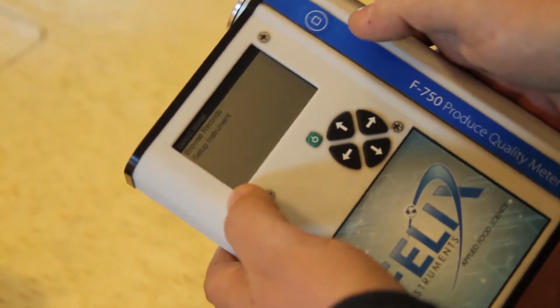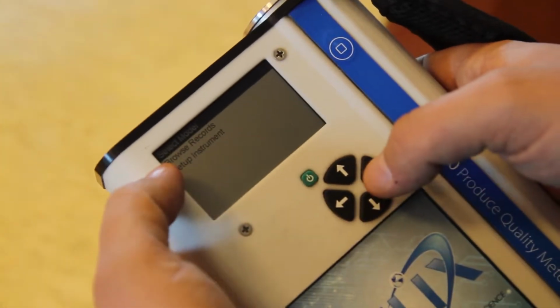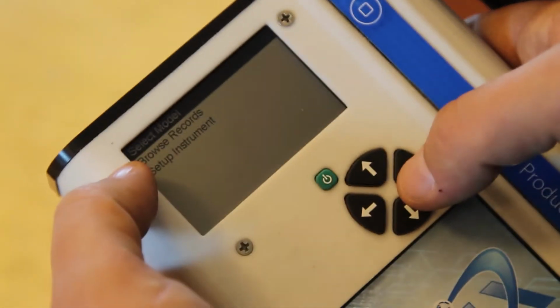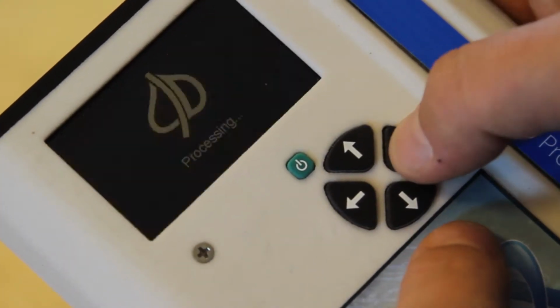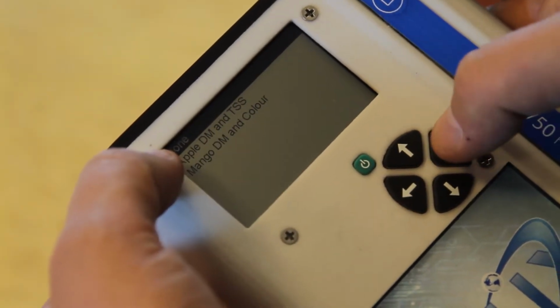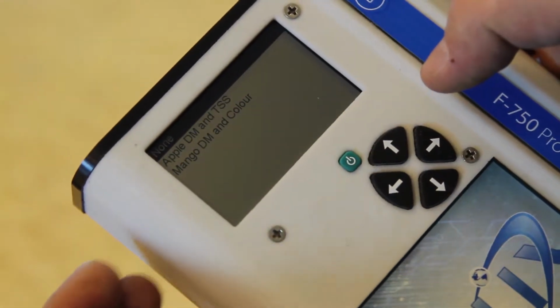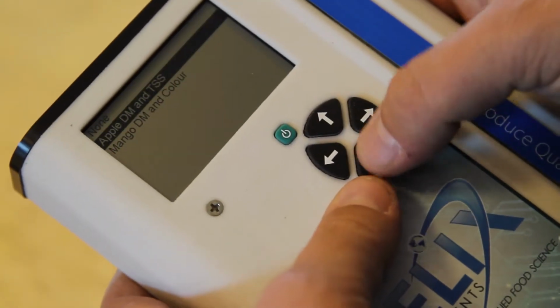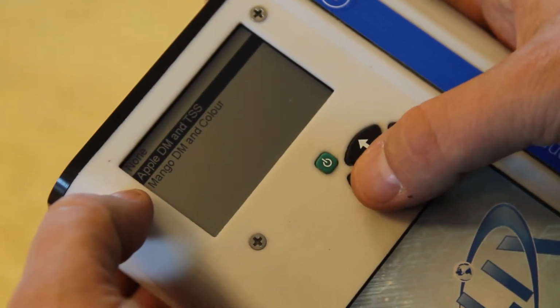To begin, we press the green power button to turn the F750 on. Immediately, we're presented with a simple list that has three options: select model, browse records, and setup instrument. We use the navigation keys to scroll right into menus. Under the select model menu, we have a list of the models that are pre-programmed on the F750.